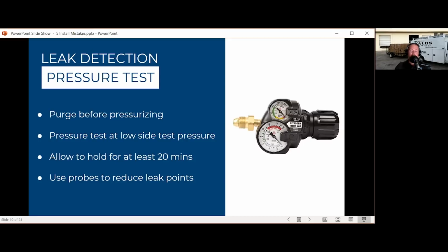I mean, it would be better if you could do pressure tests for hours. Some manufacturers specify 24-hour, 48-hour pressure tests on things like VRF systems, VRV systems. You do want to hold it under nitrogen pressure for as long as you can, and recognize that, again, every system is going to leak a little bit, but under standard nitrogen pressurization, it should be almost unnoticeable.